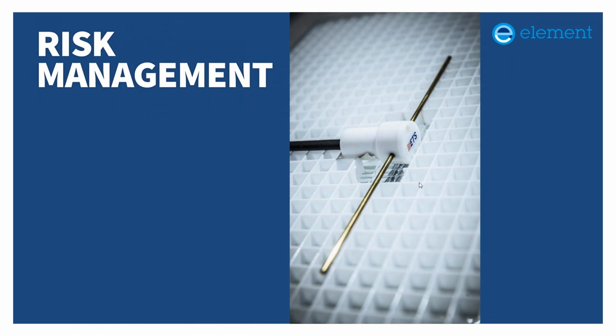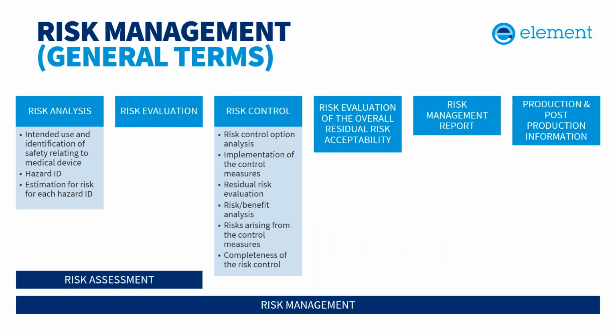And then a key concept for all medical devices is risk management. So ISO 14971 is the key standard for the risk management process for medical devices. Basically what you're doing for risk management is identifying, analyzing, evaluating, and prioritizing current and potential risks. So you start with the risk assessment, which helps you identify and categorize the risks, and it provides an outline for potential consequences. Essentially, if there is an issue, what's going to happen.